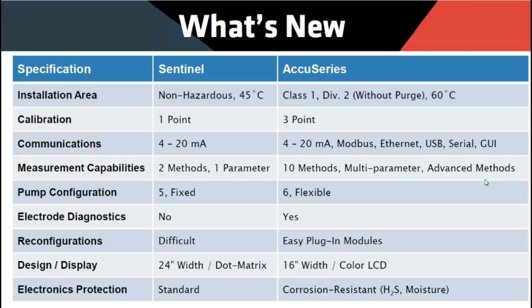Now for a multi-parameter, we have a lot of flexibility with this. The only limitation is the pumps available. So the Sentinel had 5 fixed pumps, whereas now we can do 6 of any variety, either piston or peristaltic. An example of a multi-parameter system could be an acidity, alkalinity, and pH system with 1 piston pump for the acidity, 1 for the alkalinity, and then the pH can be read from the pH electrode.